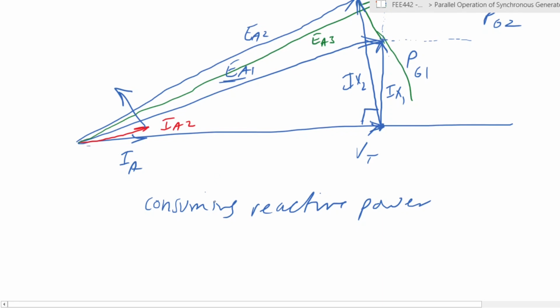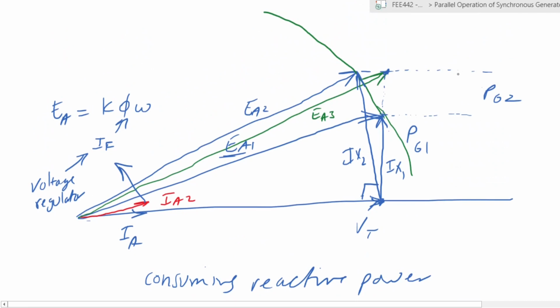So it brings us back to what we had talked about, that the reactive power is varied by the voltage regulator. And what is the voltage regulator? Voltage regulator is IF. Remember that EA is equal to K phi omega, and phi is related to the field current that we have. And field current, of course, is your voltage regulator. So what we have done here is we have managed to increase the amount of power, but we have still retained our power factor where it is. So that means that you have to regulate both the voltage and the governor, the prime mover, together in order to achieve whatever values of power and reactive power that you need to achieve.